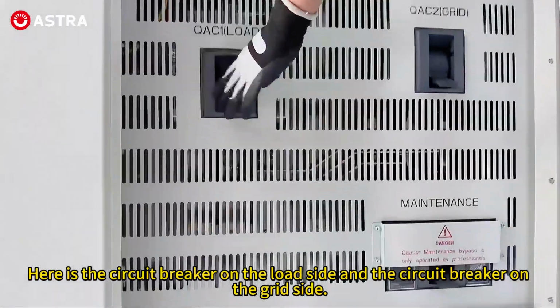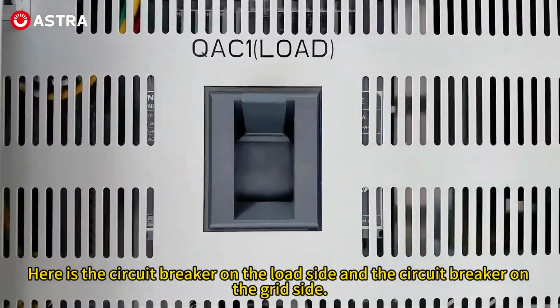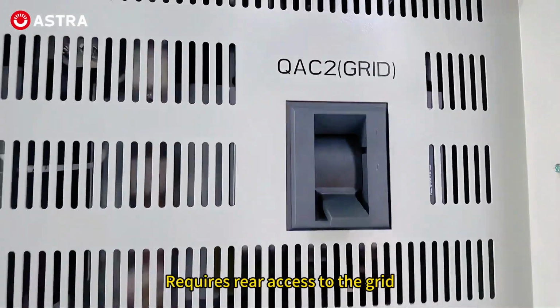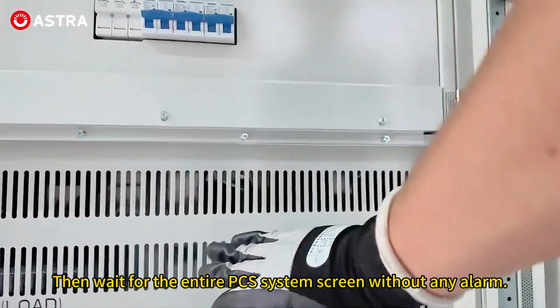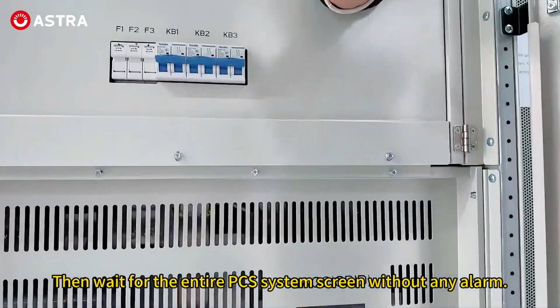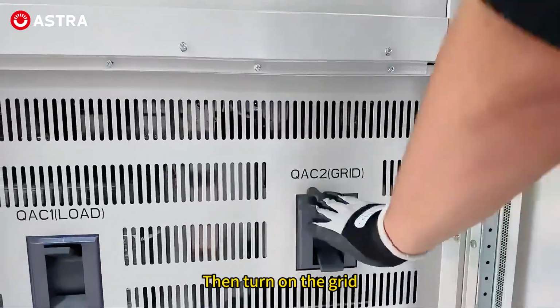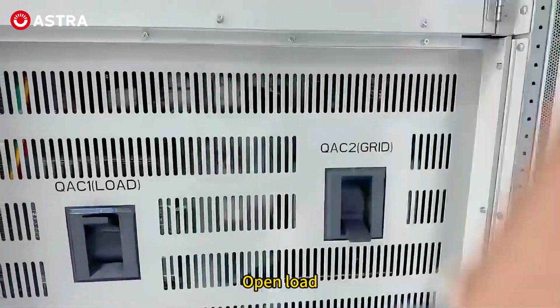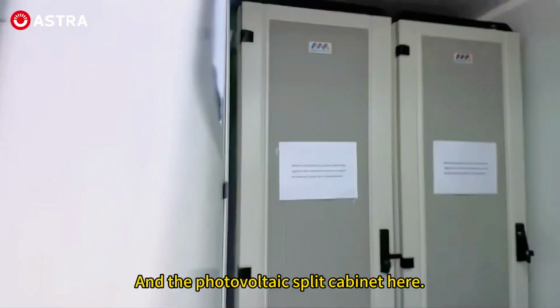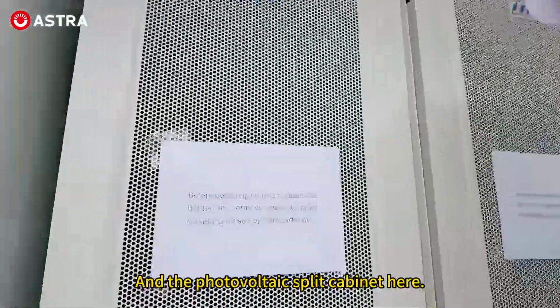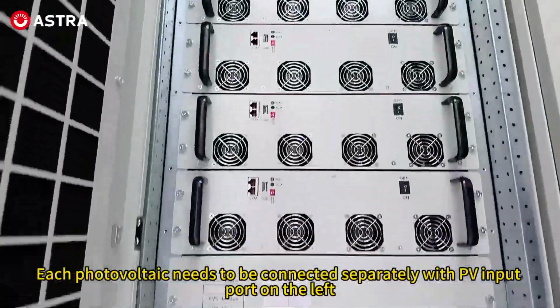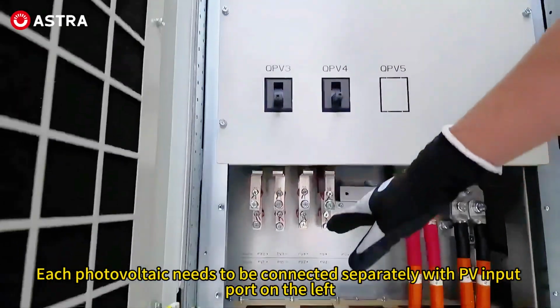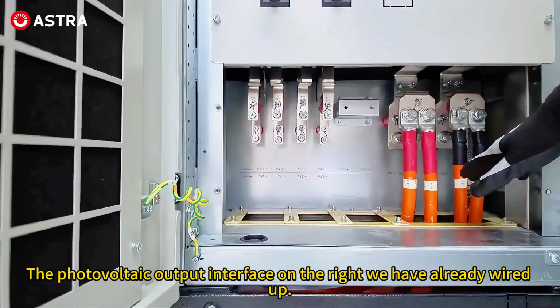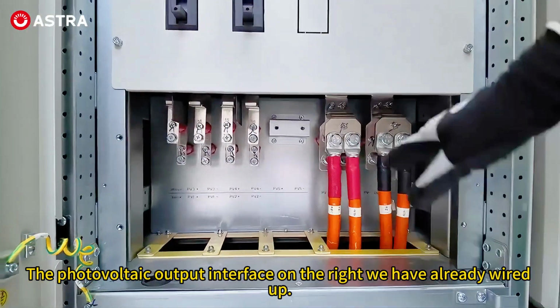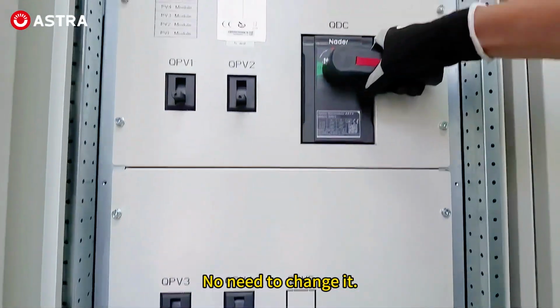Here is the circuit breaker on the load side, and the circuit breaker on the grid side. Requires rear access to the grid. Then wait for the entire PCS system screen without any alarm. Then turn on the grid. Open load. And the photovoltaic split cabinet here. Each photovoltaic needs to be connected separately with PV input port on the left. The photovoltaic output interface on the right, we have already wired up. No need to change it.